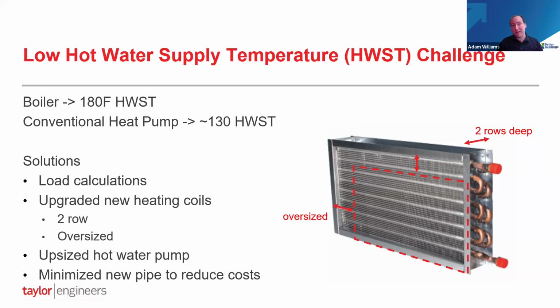And when you lower that hot water supply temperature, you need to make sure that there is enough coil capacity in the building to deliver the BTUs that you need to that space at that lower temperature. So the question is, how do we retrofit this building without having to replace everything, all the piping, all the coils? The first thing we did with any all electric retrofit is we do load calculations. We don't just match the existing equipment size, because our experience has been that many times heating systems are oversized. And that's in part, I think, because load calculation technology has gotten more sophisticated. We're less conservative with calculations and more aggressive in trying to right size this.